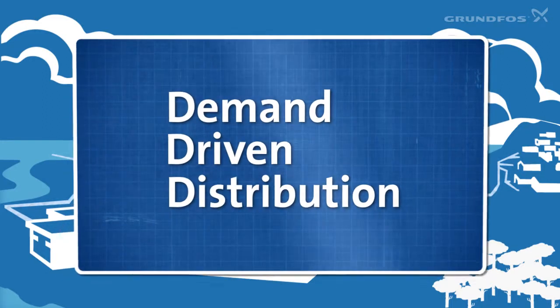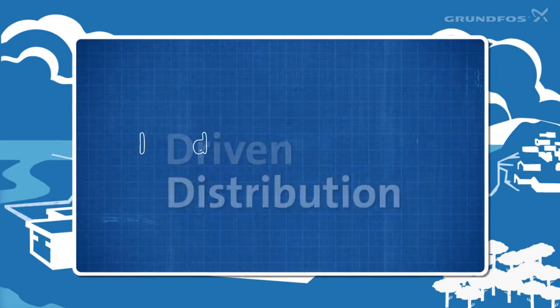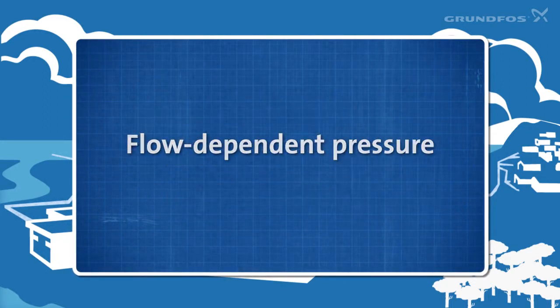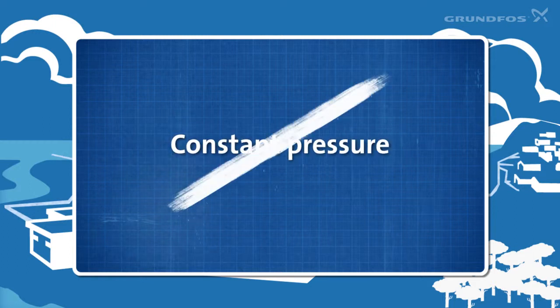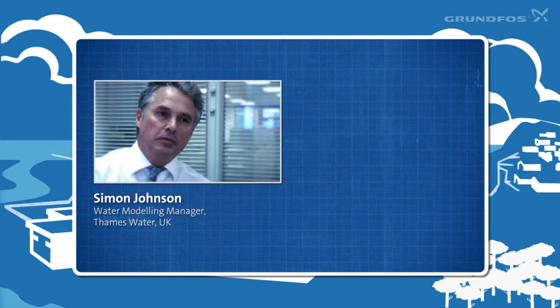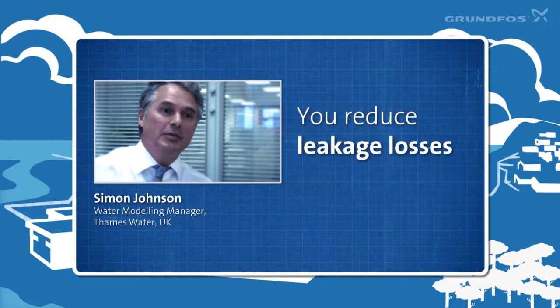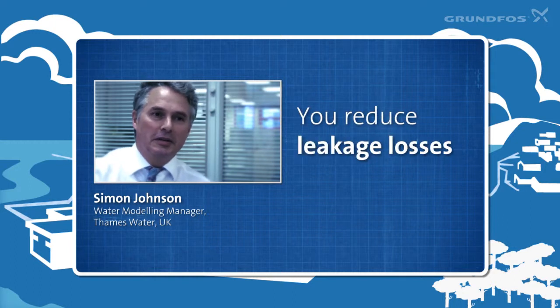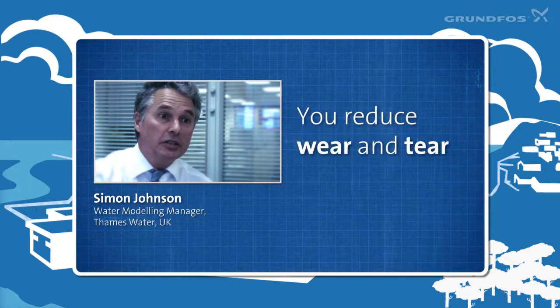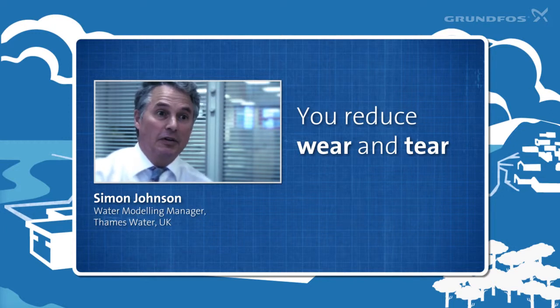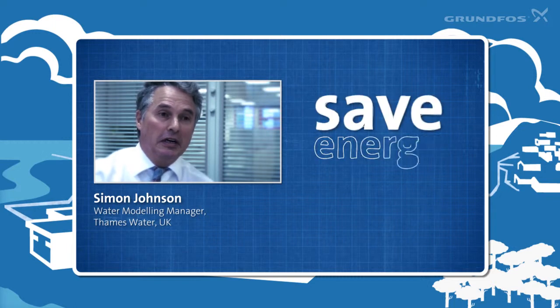A demand-driven distribution system uses flow-dependent pressure instead of constant pressure from the pump, and this creates three main benefits. As water modelling manager Simon Johnson from Thames Water explains: you reduce leakage losses, you reduce wear and tear, which cuts down maintenance costs and may even allow you to postpone investments in new assets, and you save energy.